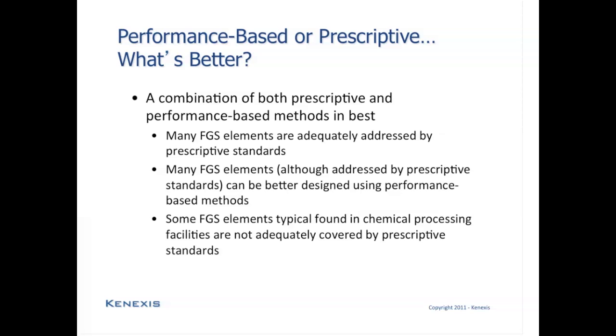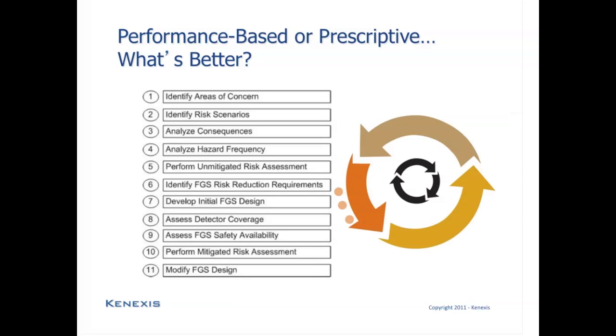But a lot of the elements, even though they are addressed by prescriptive standards, could be better designed using performance-based methods. It will allow for better detector placements and more effective determination of quantities and locations. And some FGS elements that are often found in the chemical process industries are not covered by prescriptive standards at all. So things like placement of toxic gas detectors in open areas is something that is not addressed at all by any standards that are currently available. So using performance-based techniques to address these is really the only feasible option.